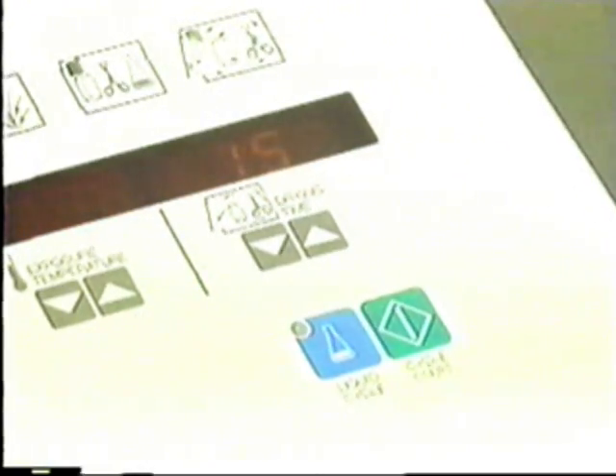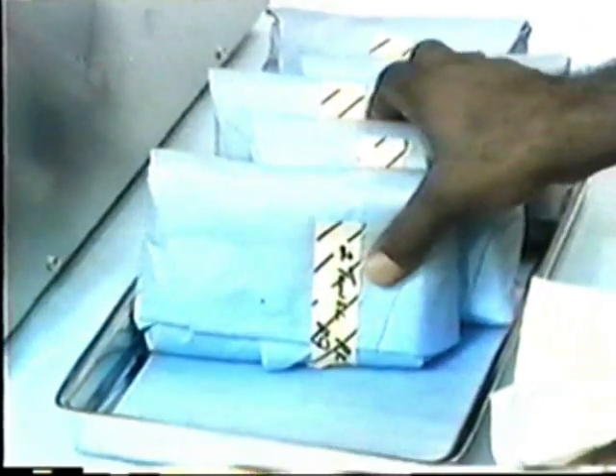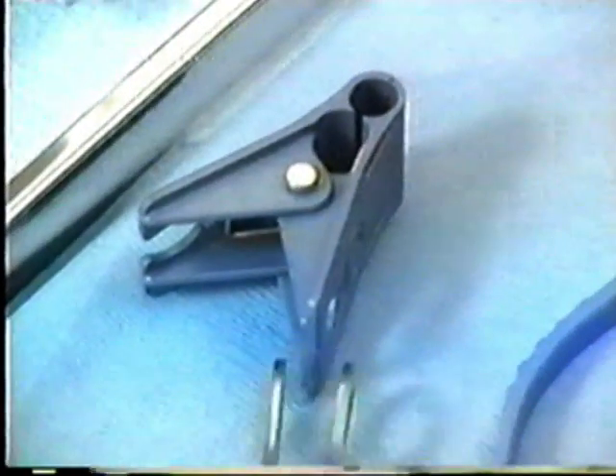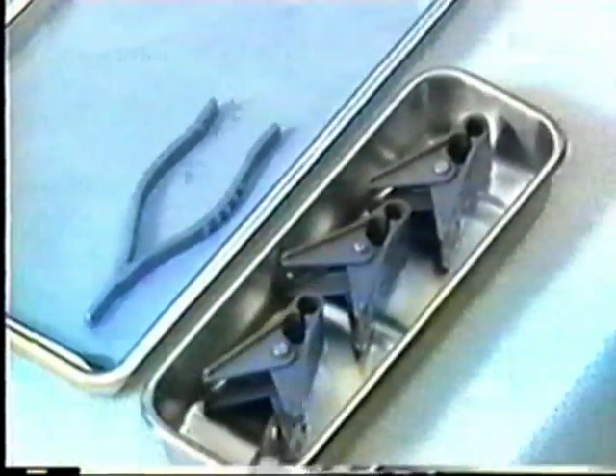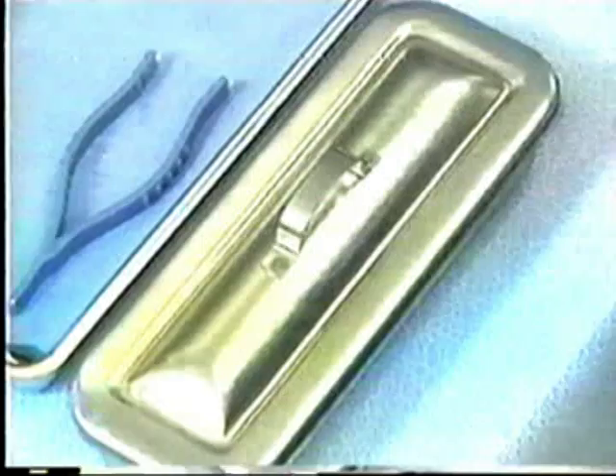Allow the contents to dry for approximately 15 minutes before removing them. If you open the sterilizer door completely, this allows condensation due to the outside cool air and results in wet packs. Some modern autoclaves have an automatic drying cycle. This eliminates a drying step. All dry, wrapped, and unwrapped items that need not remain sterile may be removed with your clean, dry hands. Check all sterilization indicators for proper changes in color. Remove unwrapped sterile items with sterile transfer forceps and place these items in a sterile environment or sterile storage container.